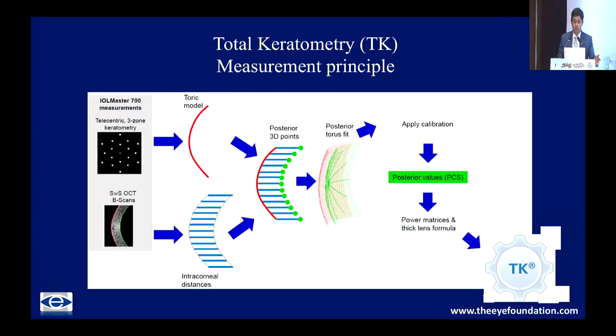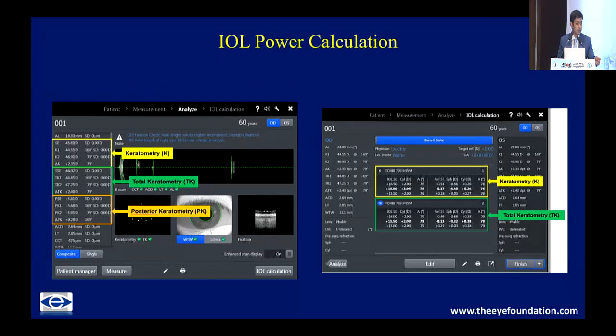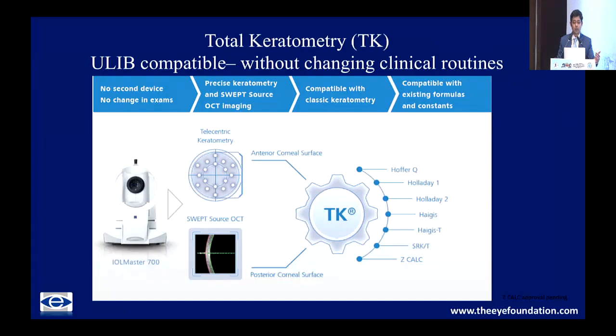Going further, we have this total keratometry concept, where essentially we all understand the importance of measuring the posterior cornea, especially for toric IOL calculations. The total keratometry gives us a toric model where it measures the central 3 mm cornea and also gives us the posterior toric fit. That is, it measures the posterior points directly from the posterior surface of the cornea. And while we did already have devices which could look at the posterior corneal power and posterior corneal astigmatism, they did not give us a symmetric measurement between the anterior and posterior. This is really important because we can now devise formulae based on this total keratometry, and these total keratometry formulae are ULIB compatible, so you don't really have to change clinical routines to measure it.